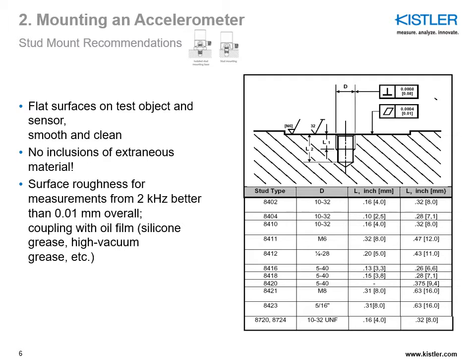Heavily anodized aluminium studs may be scratched and no longer insulated adequately. On the other hand, if you use studs with a ceramic insert, depending on the design, you may not have adequate transverse rigidity, and the upper temperature limits can also be very critical in such cases.